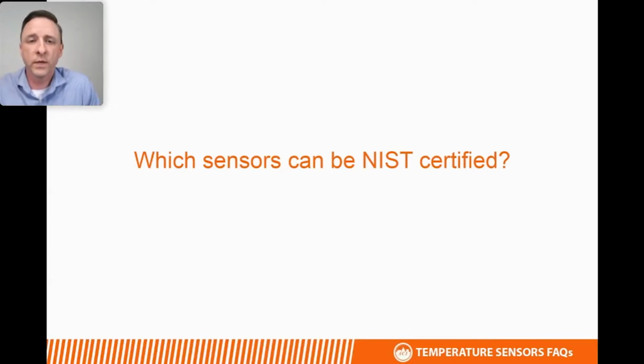More common question in recent years is which can be NIST certified. And just about every single one of our temperature sensors can be provided with an NIST certificate. There's only very limited exceptions. Primarily, those exceptions are based on the physical size of the sensor. For example, rigid averaging, if a probe is longer than 36 inches, it won't physically fit into our testing chamber. And then we also have some LCD wall sensors that we're not able to provide with an NIST certificate.